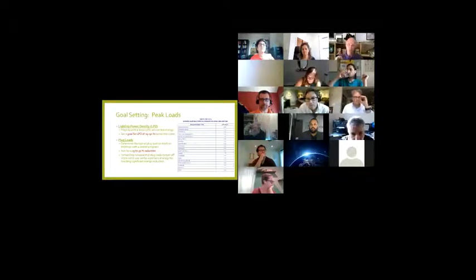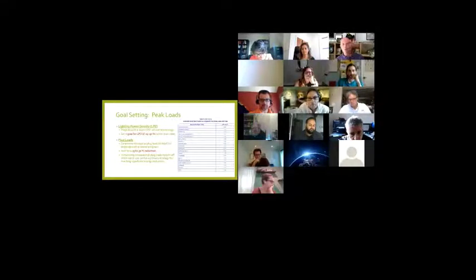It can be an order of magnitude lower than what the nameplate exercise gets you—instead of 10 watts a square foot, it's actually closer to 1 watt a square foot or less. If you size mechanical and electrical systems for 10 watts a square foot, you've oversized them and spent way too much money. Besides, they don't operate well when the load is that low. So take the time to figure out the real load on your plug load systems.